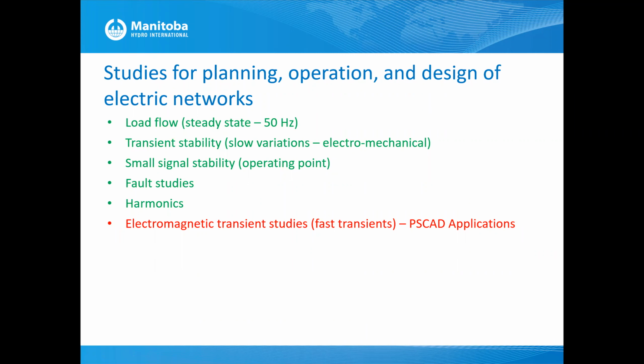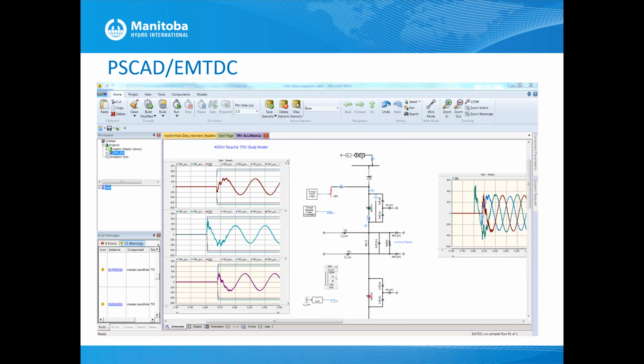However, electromagnetic transients allow you to perform very fast transients. It looks at extreme high frequencies, known as ultra high frequency, all the way down to electromechanical modes. You can carry out all the above studies, though we don't generally recommend it, because it takes longer to perform these studies in PSCAD than with RMS tools, but it's something that can be done.